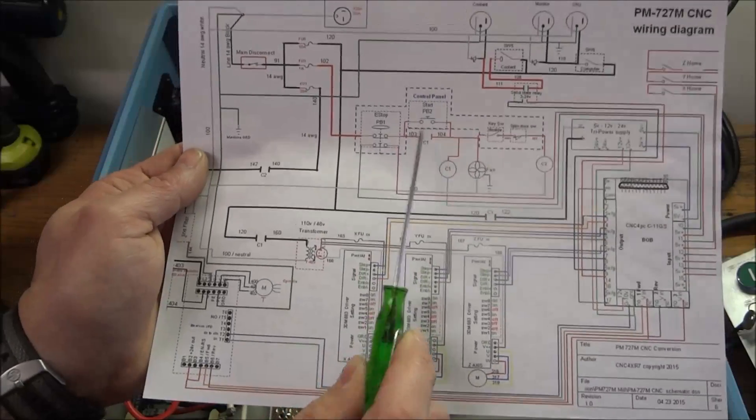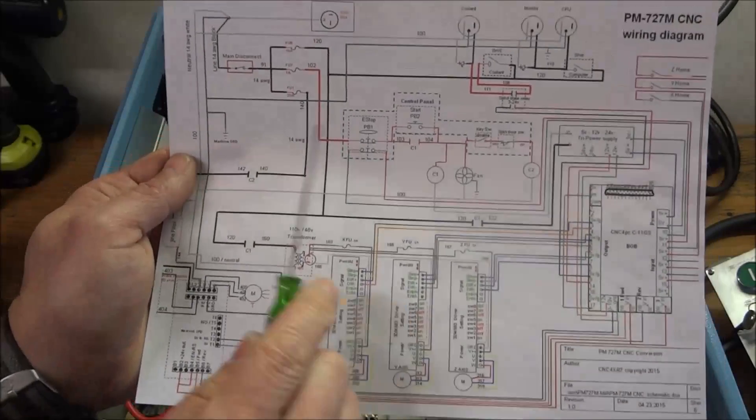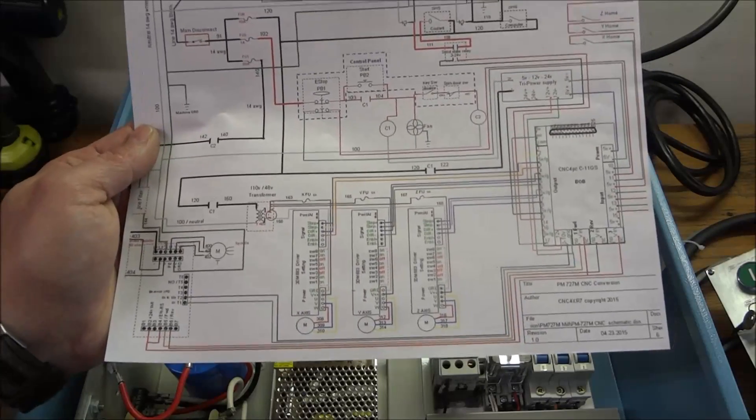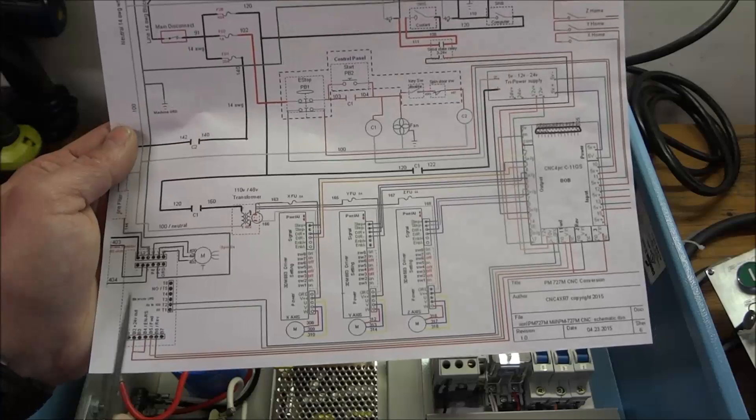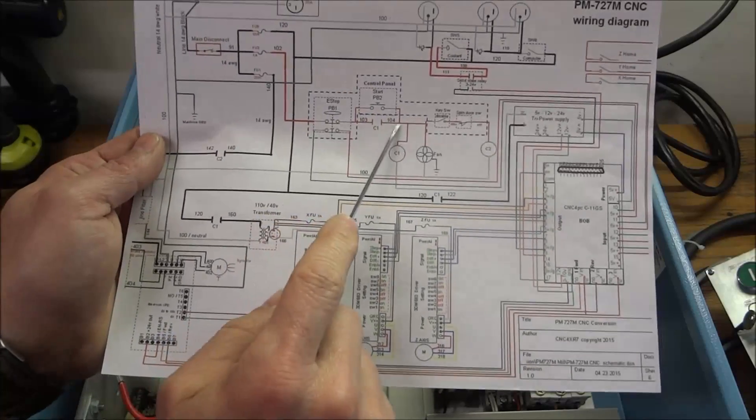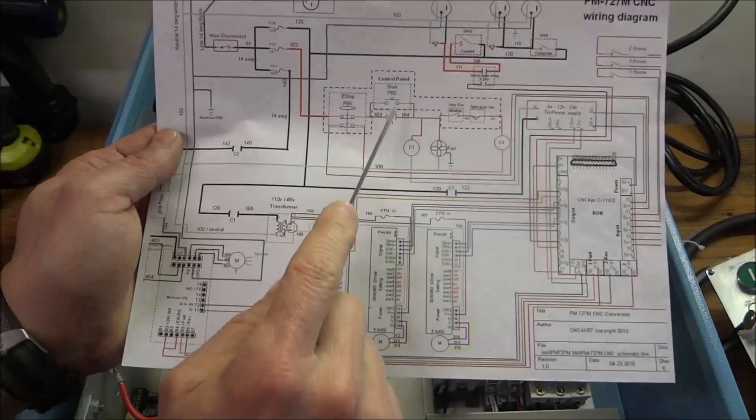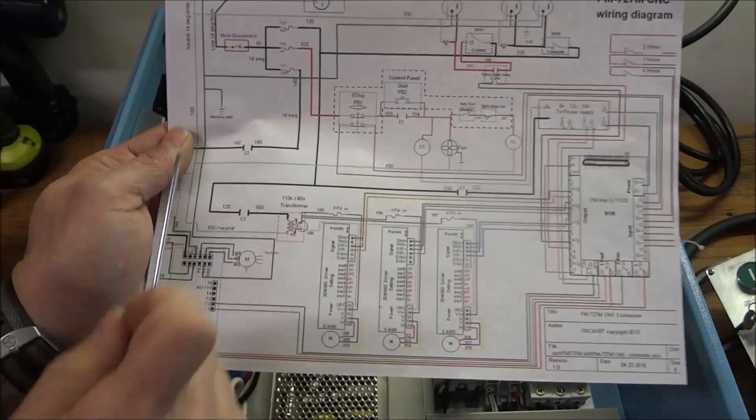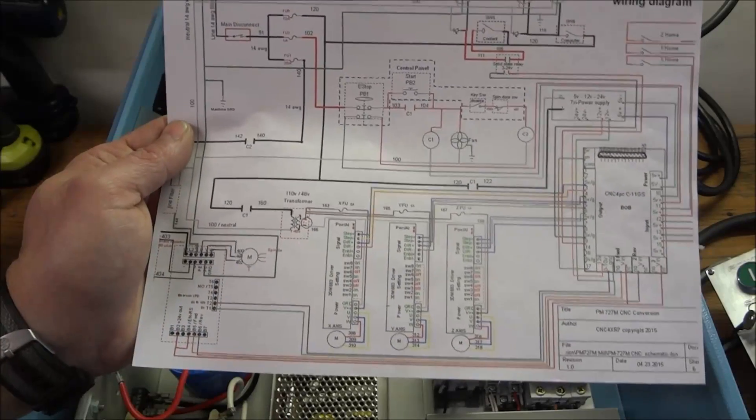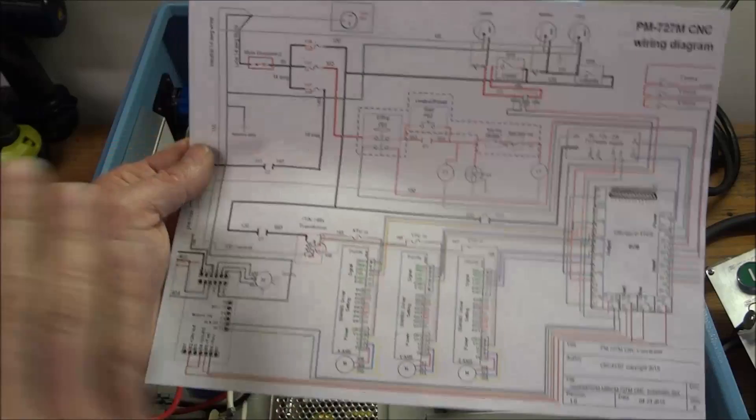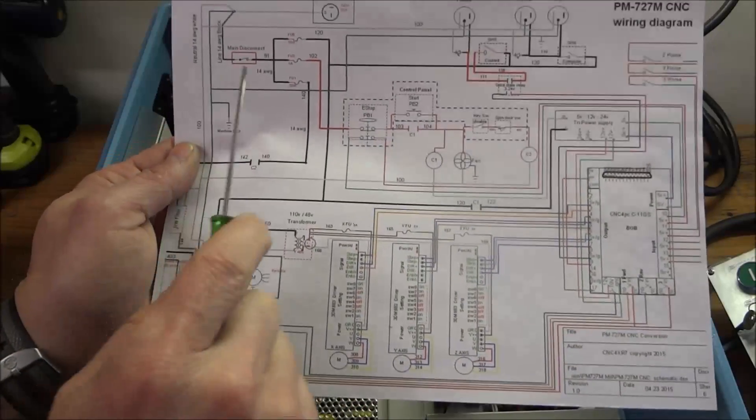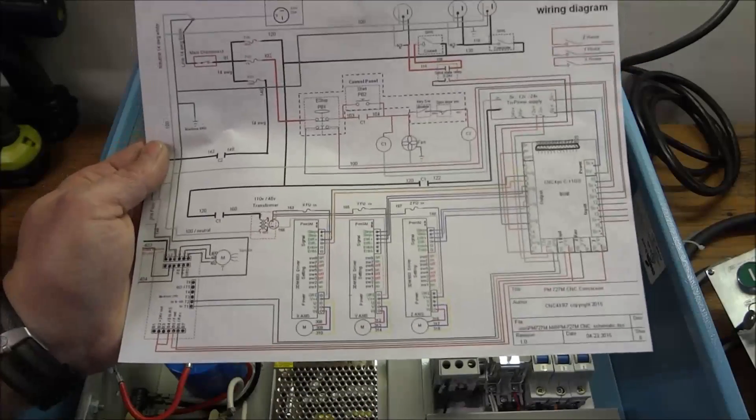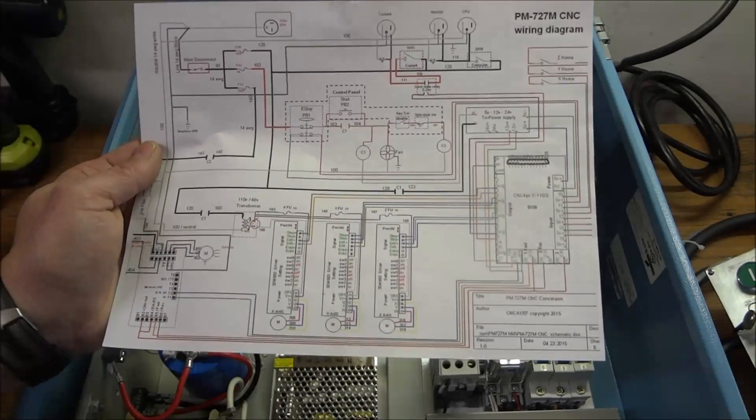Now why do we need this? Let's say you're running your machine and the power goes out. If you didn't have this and you just had this ran straight through without the push button and without the coil, without the contacts here, if you lose power then the machine is going to shut down. But as soon as power is reapplied, these are going to re-energize and your machine is going to start back up. That's not a good situation to be in.